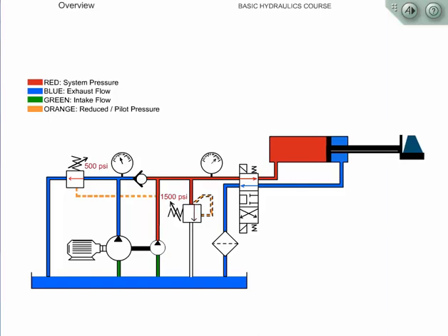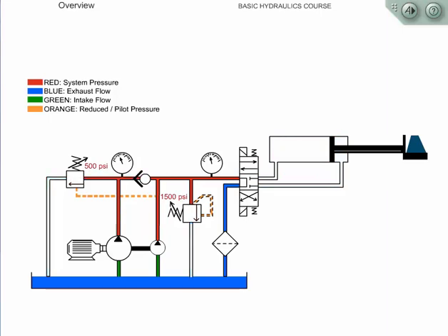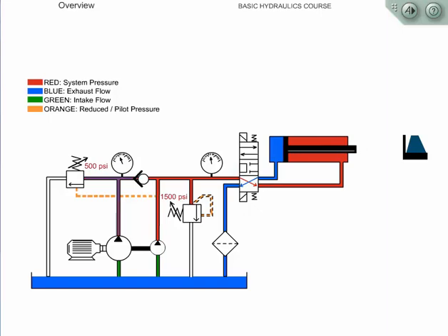The low-volume pump continues to deliver flow for the higher pressure requirement of the work cycle. Once the flow from the high-volume pump is unloaded, both pumps join once again for a rapid return of the cylinder. The high-low system requires less input power to meet the work cycle's speed and force requirements.